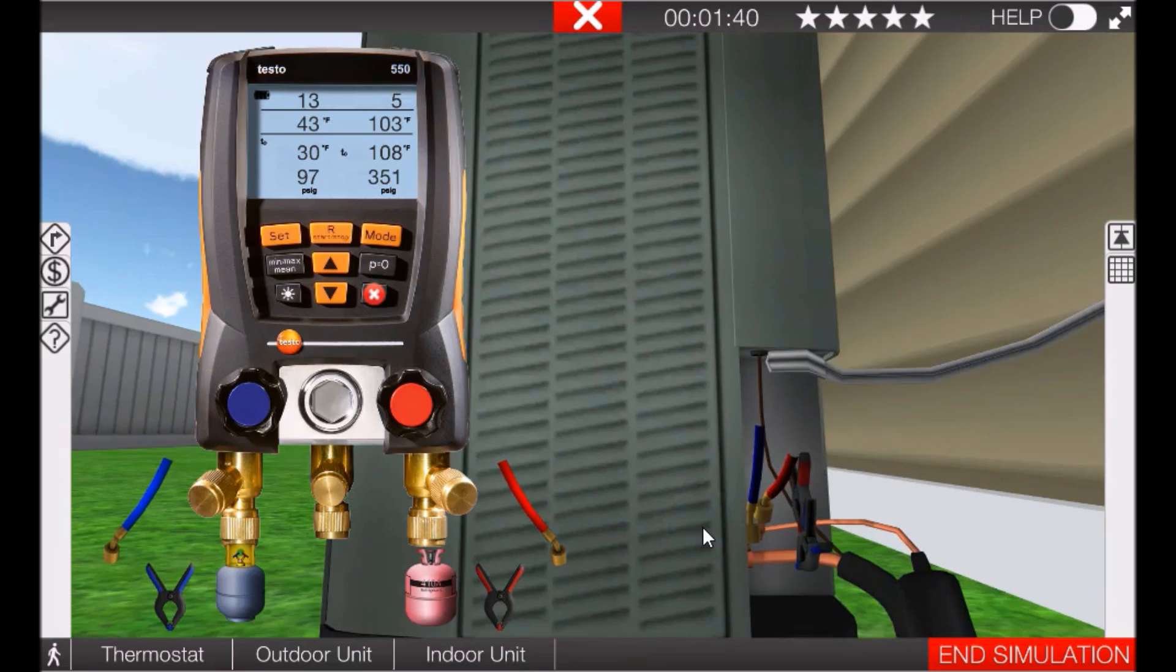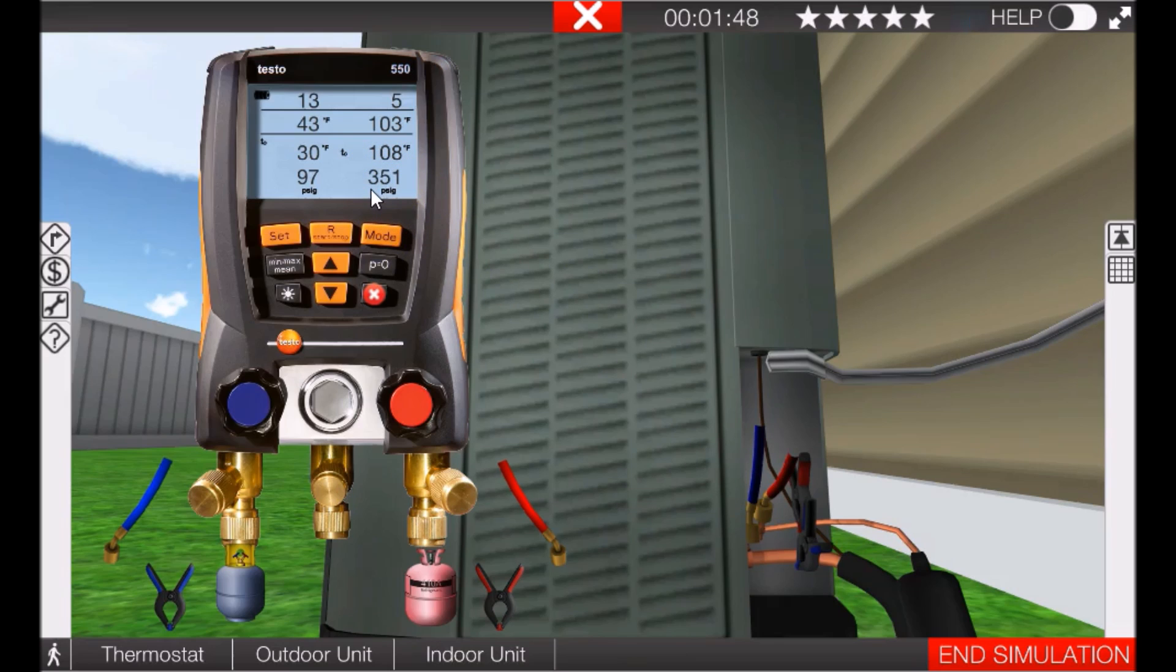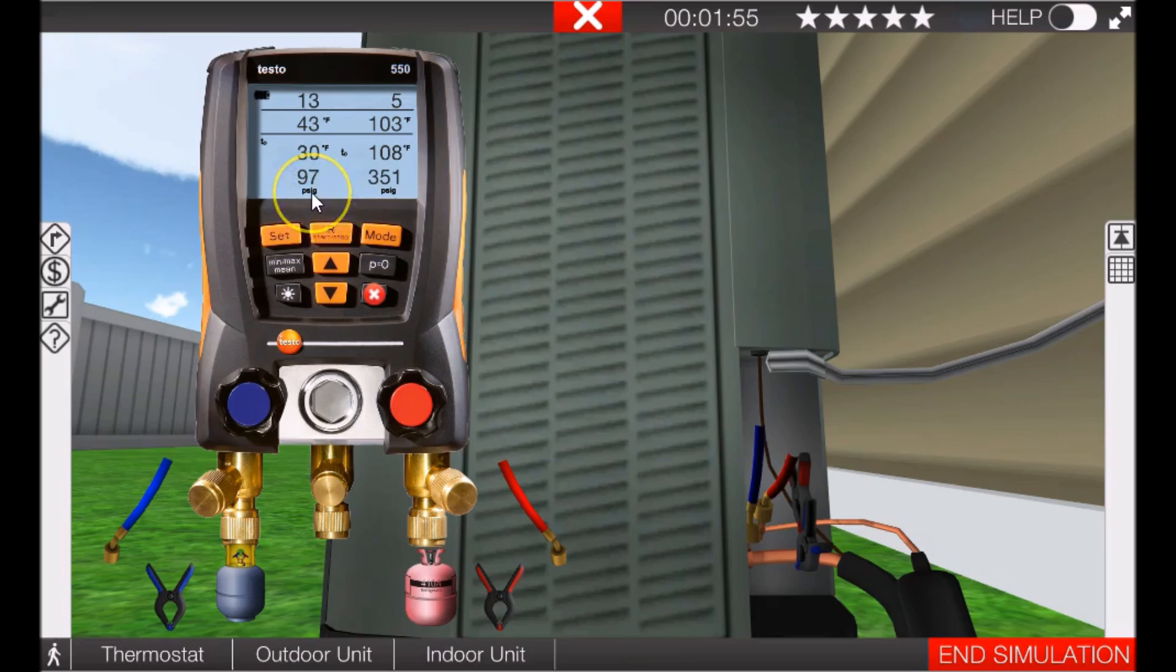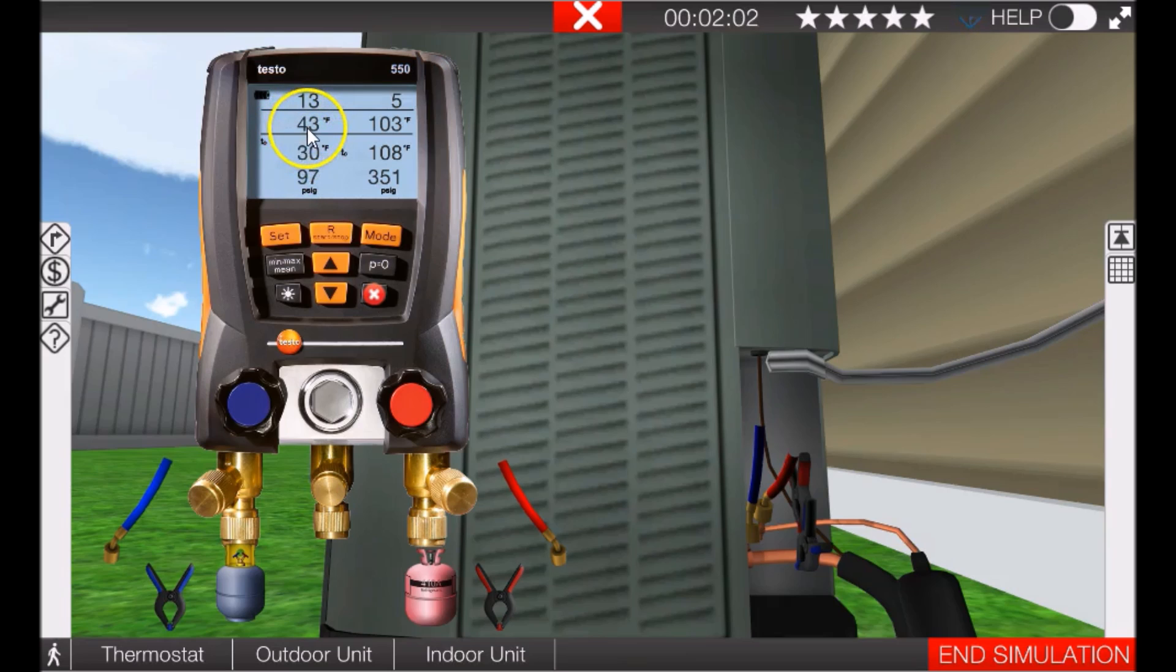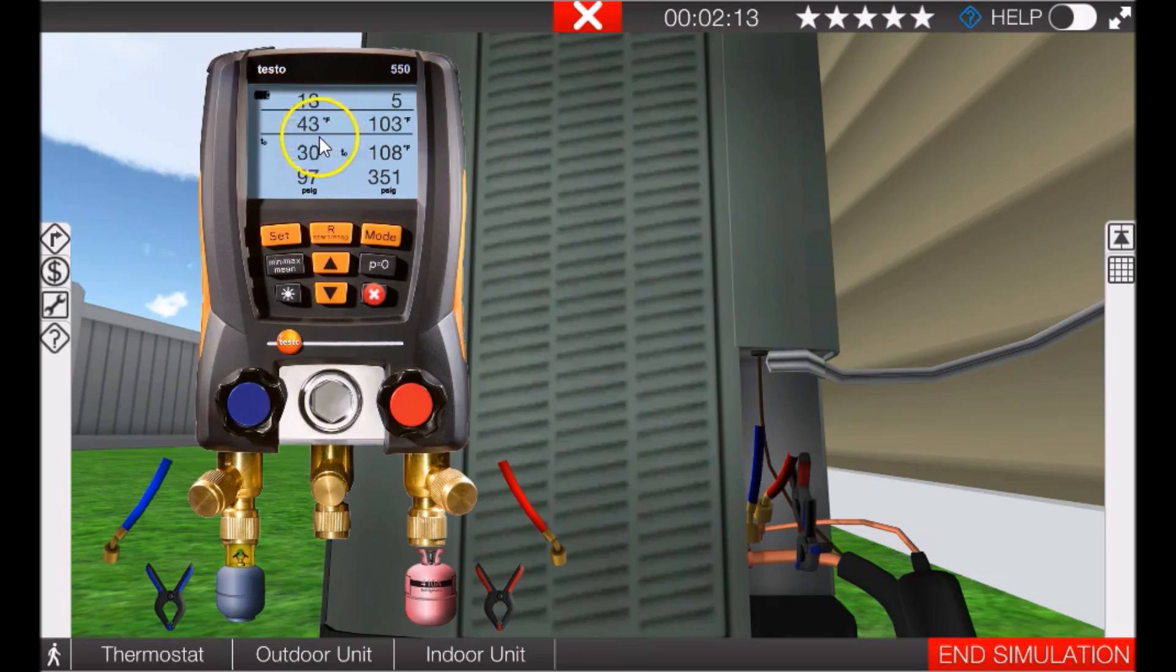Okay, so here's what we're looking at. We have 351 psig on the high side, saturation temperature of 108 degrees Fahrenheit. 97 psig on the low side, saturation point of 30 degrees Fahrenheit. Our line temperatures are 43 and 103 respectively. So we have 5 degrees of subcooling and 13 degrees of superheat.